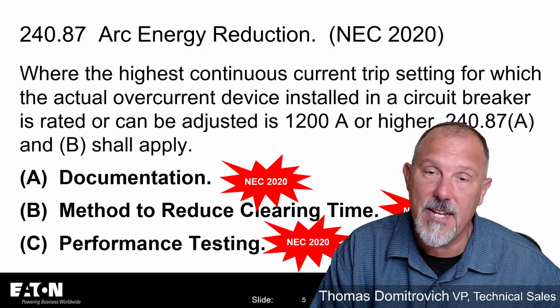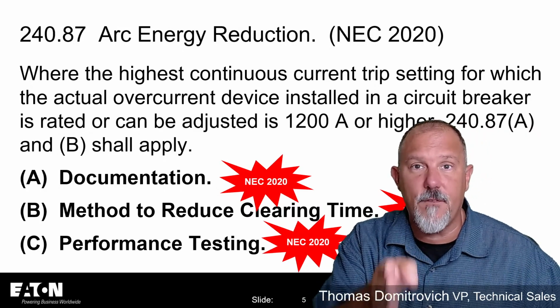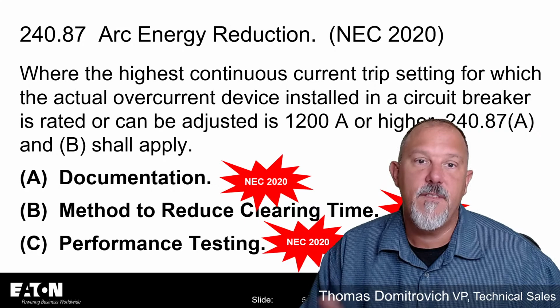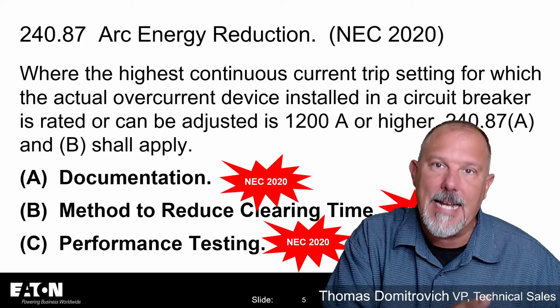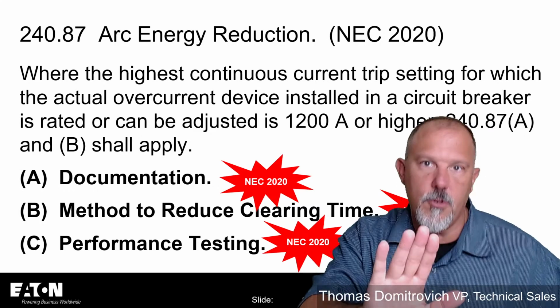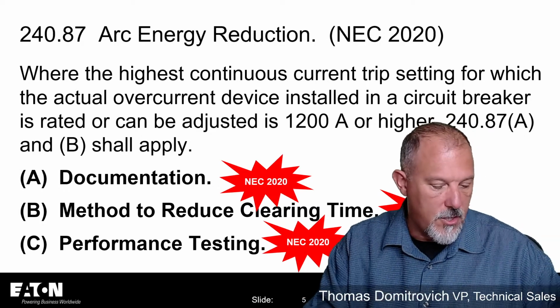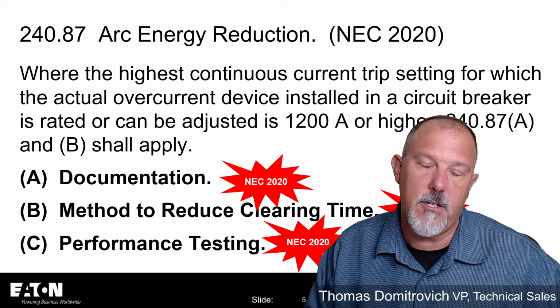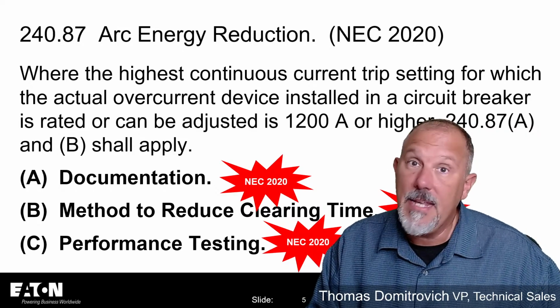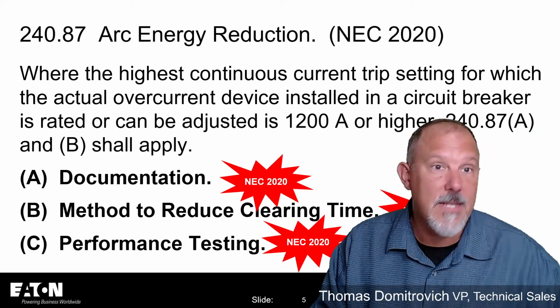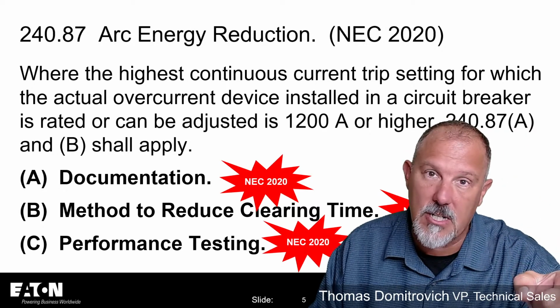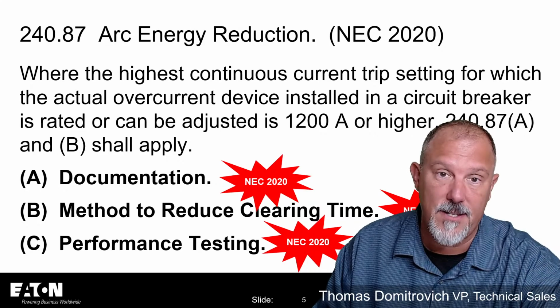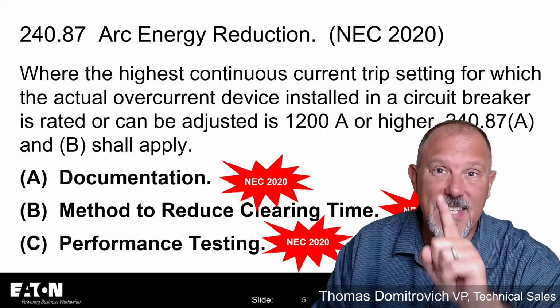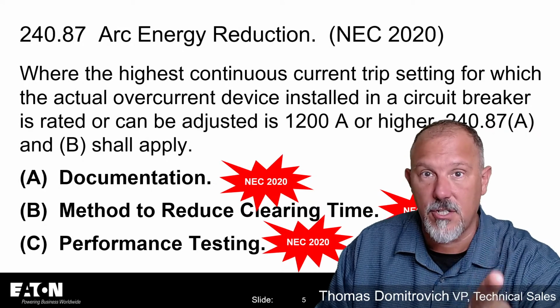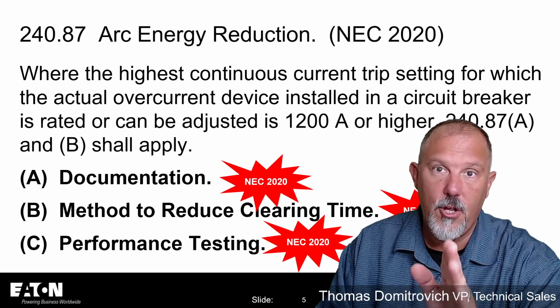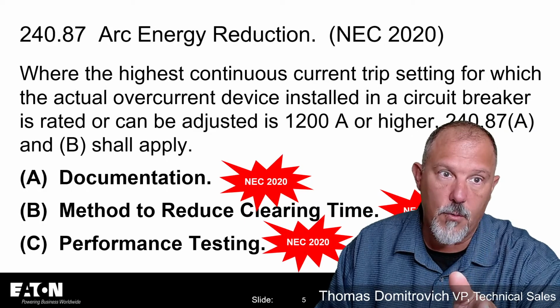Same thing goes for 1,000 amps on ground fault protection of equipment. If I have a 1,000 amp frame, well, you can't buy a 1,000 amp frame. If I have a 1,200 amp frame and I adjust it down to 800 amps, and I put the little lockable door on it, or based upon the latest version of the code, I can have password protection in the 2020 code. That does not mean that you don't have to have GFPE. That does not mean you don't have to have an arc reduction technology, because you can still adjust it to 1,200 amps. That's the key. If you can adjust that circuit breaker to 1,200 amps, then you have to get into 240.87.